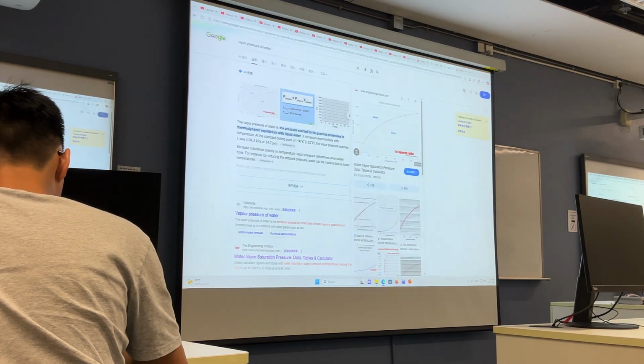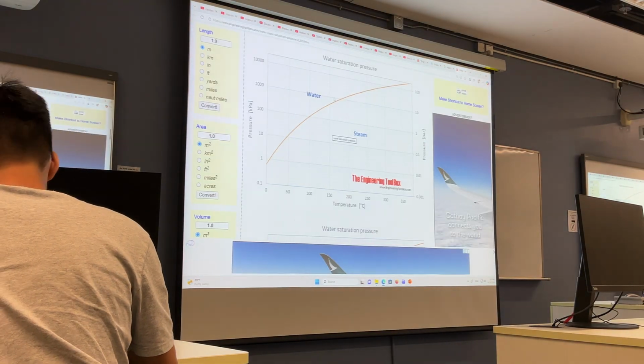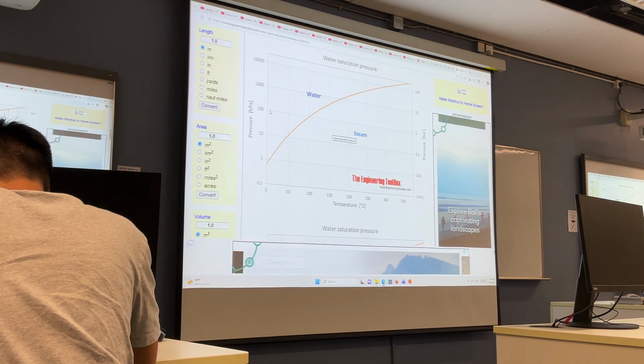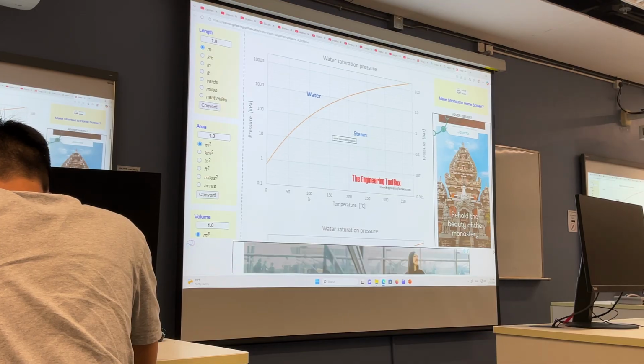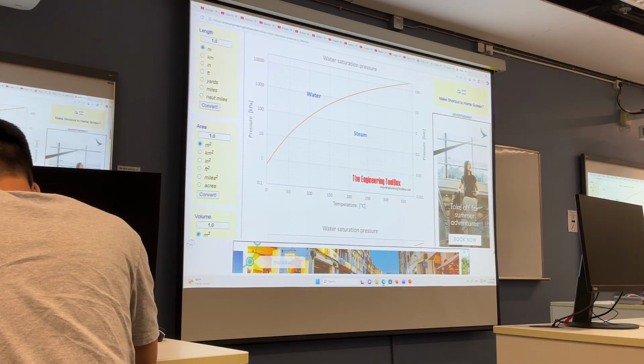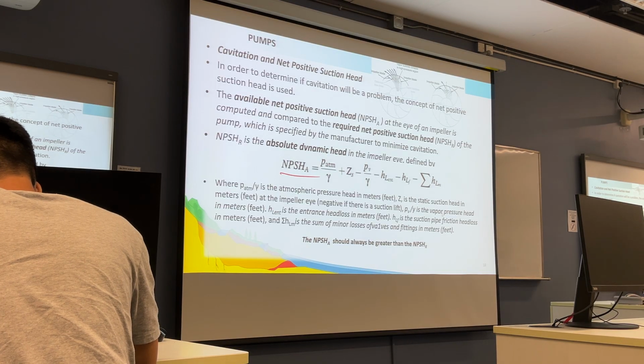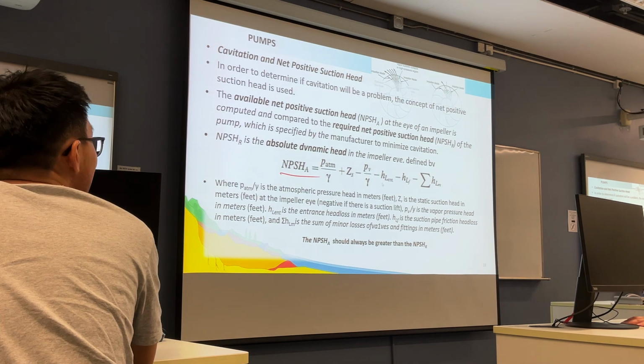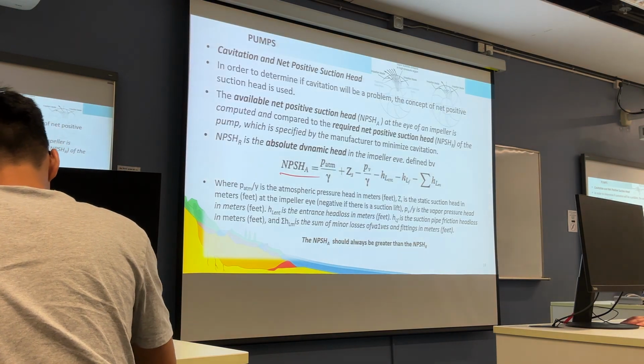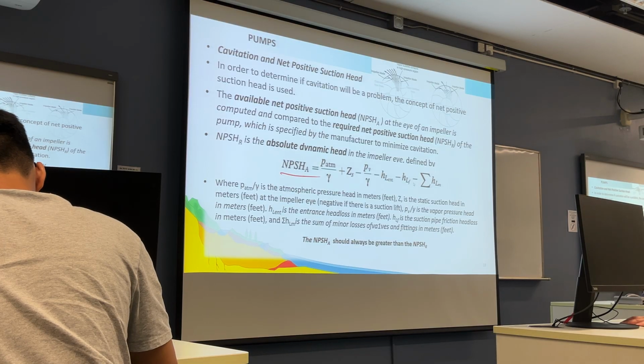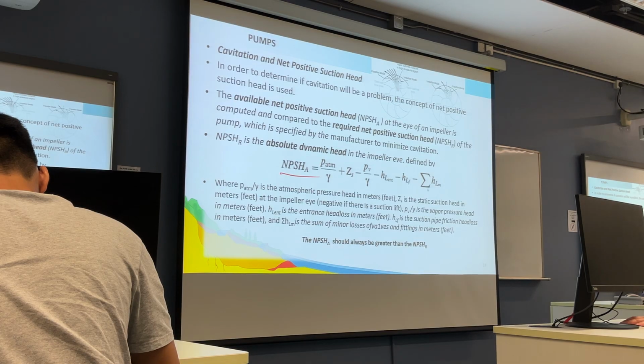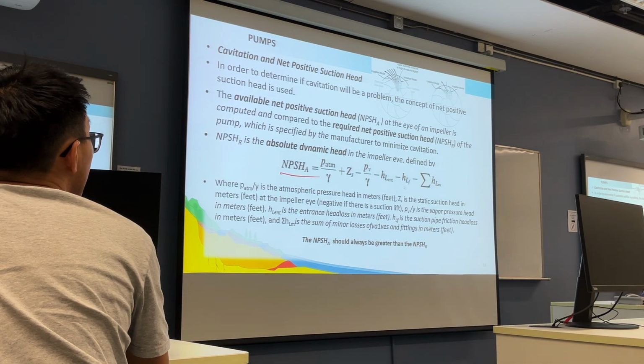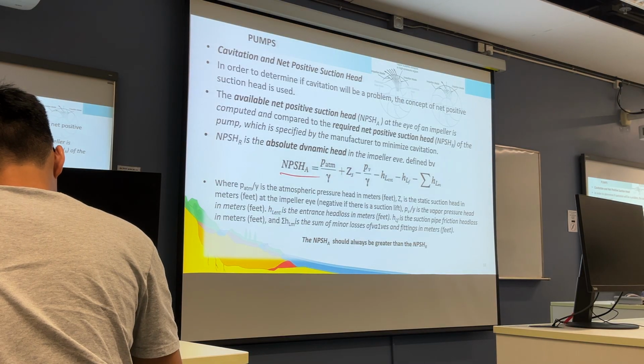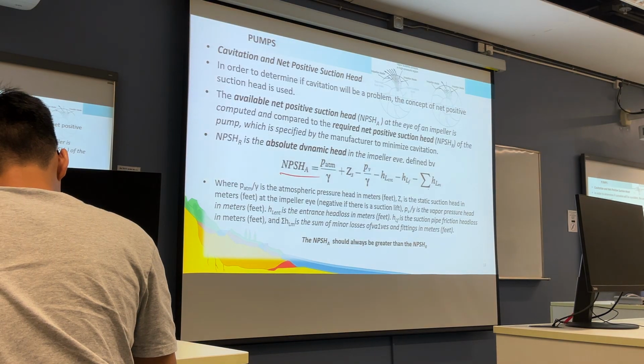It should be referred to this figure. Okay, you can find it if necessary. Usually for this temperature, so it's 100 kPa. The vapor pressure head, and then the H_LENT, the entrance head loss, and the H_LF, maybe in the suction side there is a pump valve or other components. There may be the expansion or maybe the pipe bends, and H_LM, this is the pipe head loss, friction. This is the minor loss, which comes from the components and fittings in the suction side.